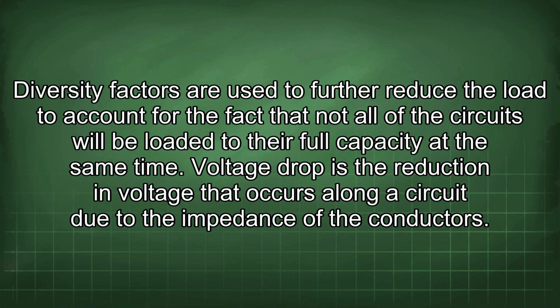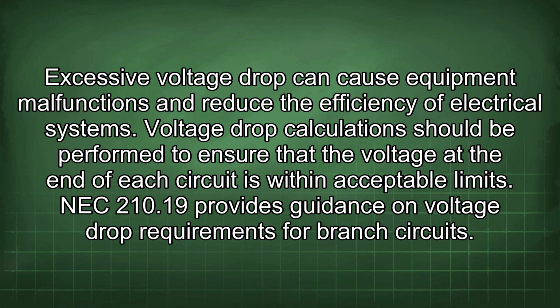Voltage drop is the reduction in voltage that occurs along a circuit due to the impedance of the conductors. Excessive voltage drop can cause equipment malfunctions and reduce the efficiency of electrical systems. Voltage drop calculations should be performed to ensure that the voltage at the end of each circuit is within acceptable limits. NEC 210.19 provides guidance on voltage drop requirements for branch circuits.